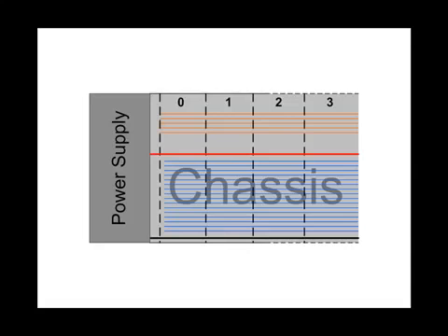Even if the PLC power supply has a surplus of power and a means to connect to your field devices, to connect them to the PLC power supply is not good practice. If a short occurs in the field wiring, and the fuse blows in the power supply, you have disabled the PLC as well.